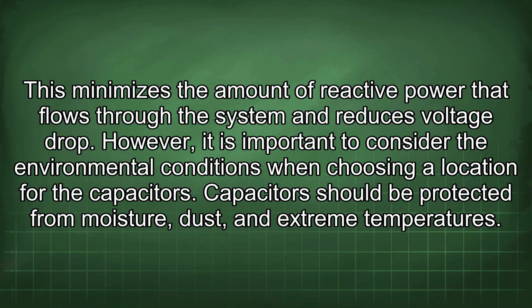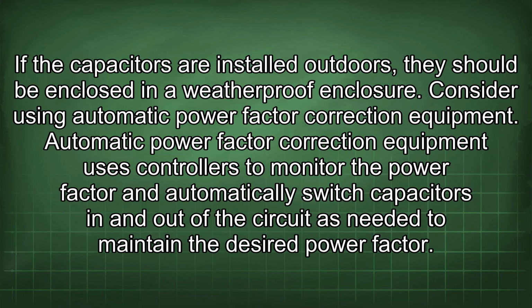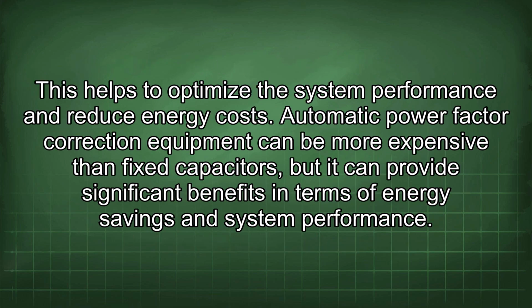However, it is important to consider the environmental conditions when choosing a location for the capacitors. Capacitors should be protected from moisture, dust, and extreme temperatures. If the capacitors are installed outdoors, they should be enclosed in a weatherproof enclosure. Consider using automatic power factor correction equipment. Automatic power factor correction equipment uses controllers to monitor the power factor and automatically switch capacitors in and out of the circuit as needed to maintain the desired power factor. This helps to optimize the system performance and reduce energy costs. Automatic power factor correction equipment can be more expensive than fixed capacitors, but it can provide significant benefits in terms of energy savings and system performance.